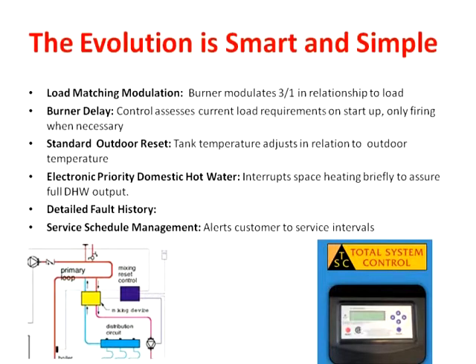It has a standard outdoor reset that comes with the unit. You have just a couple, three different parameters you put into the system, and then the tank actually adjusts according to outdoor temperature. So as it gets colder outside, the tank temperature will go up. I should note here that there's about a 20-degree difference between the temperature in the tank and what will be delivered out to, call it, the radiant floor heating system, because of the differential that you experience in going across the heat exchanger. That is the plate heat exchanger inside the module.